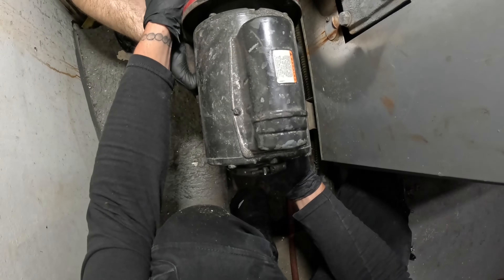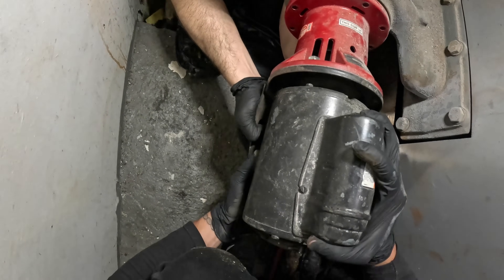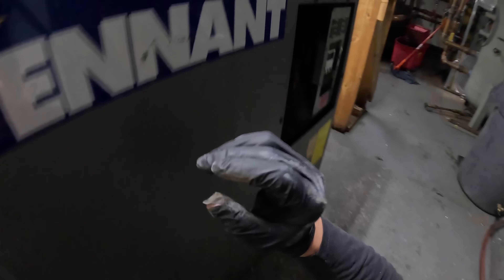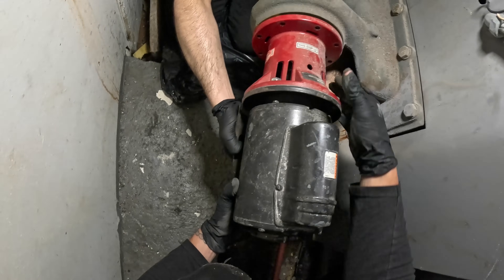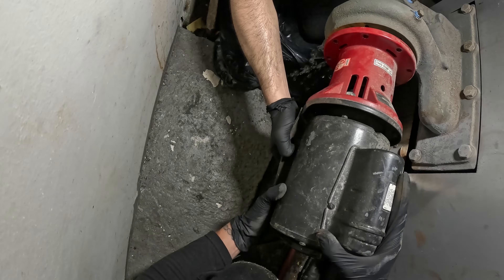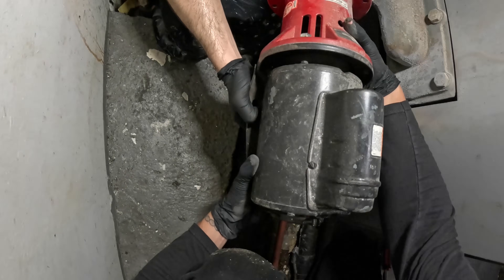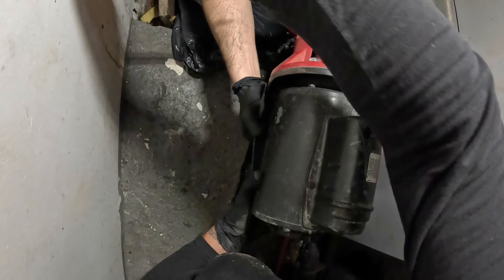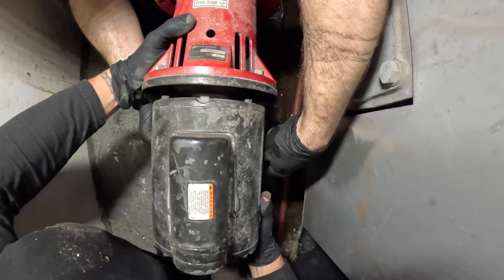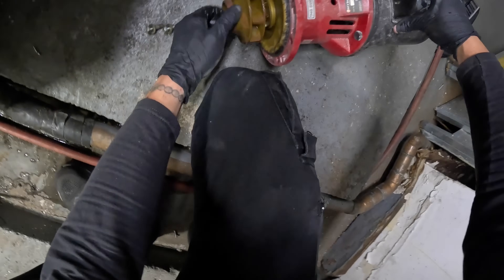Bolts are about out — okay, just stuck on there a little bit. Hold it good. We're gonna get this out — don't go too crazy. Watch your hands, water's gonna come out. Step back — it's hot, be careful. Put a garbage bag down there. That popped out. And it's out! Wow — the impeller is actually damaged. Wow, check that out.